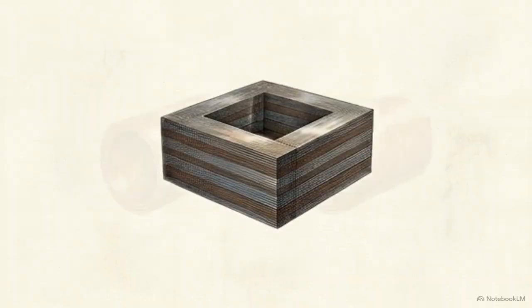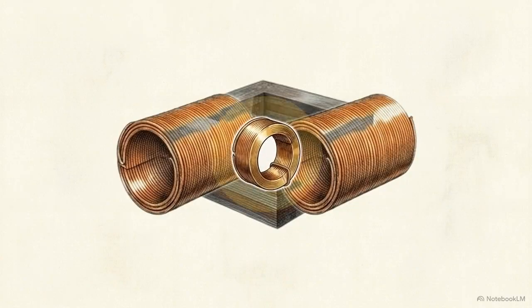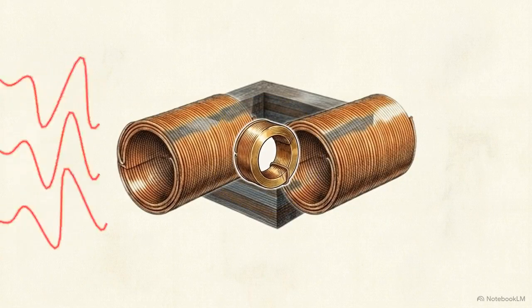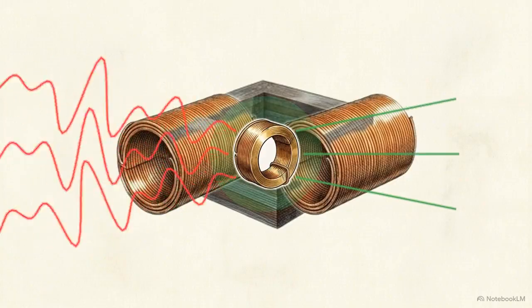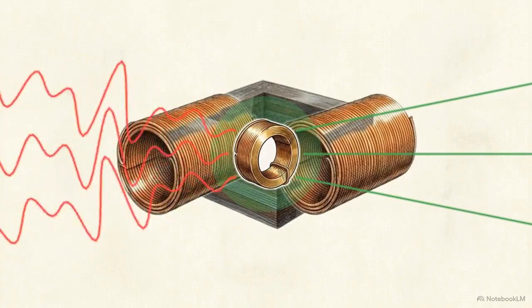Inside these autotransformers, there is often a hidden tertiary winding. This is a third, unloaded coil specifically designed to absorb and stabilize dangerous harmonic frequencies that bounce around the grid.